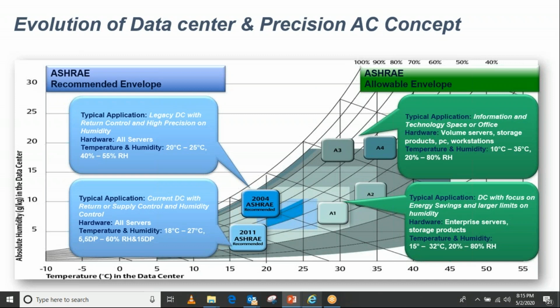Imagine you raise the chiller temperature from 7/12 to 20/27, which is a trend right now, or 18/25 in the chiller. What kind of saving will you get from 7/12, which used to be the earlier temperature, to this kind of high chilled water temperature? How are you able to raise the temperature of the DX unit on the return air side from the 22 to 24 we discussed in the previous slide to up to 35, 37 or 38 degree return air? When you maintain a much higher cold air temperature, even if your server delta is 12 or 10 degrees, your return air temperature becomes much higher. Let us take an example.